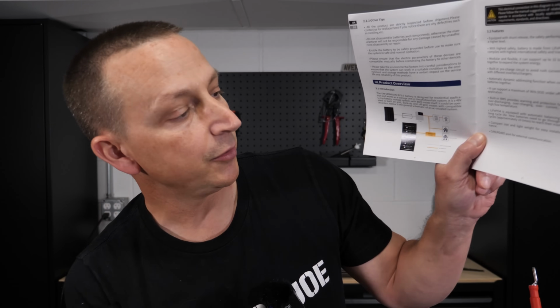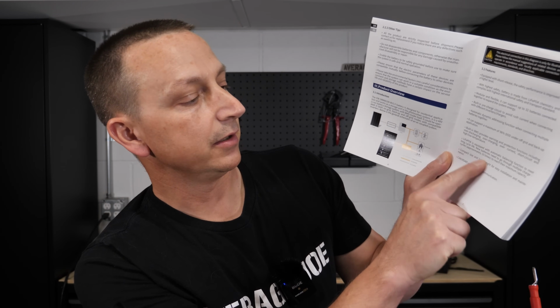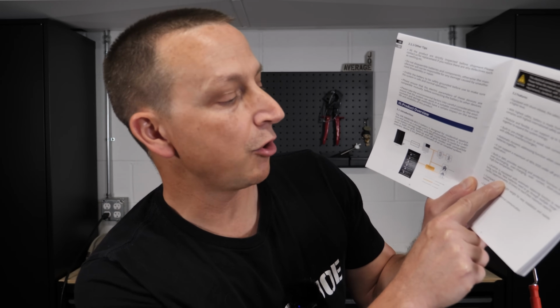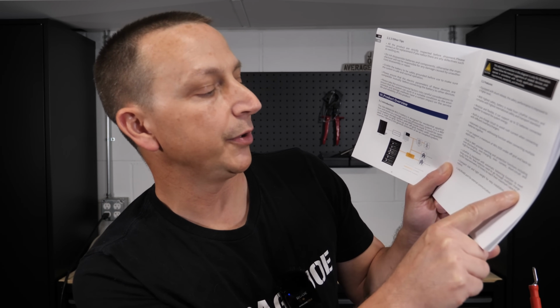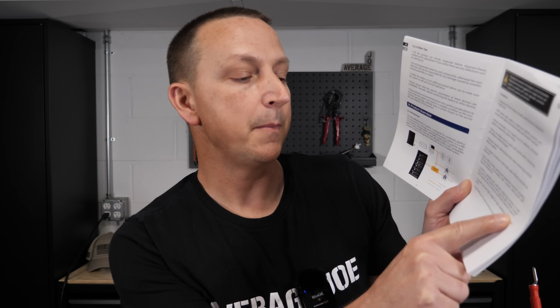Quick side note: in the manual on page 7, it says new batteries need to go through multiple charge cycles, approximately 10 times, to reach their maximum capacity. That note is probably there because people complain they're not getting 100 amp hours, but you need to allow the battery time to top balance all the cells. That's what those 10 cycles do - every time you drain it down and charge it back up, they get a little more in balance. Basically, you're allowing the BMS to do its job.